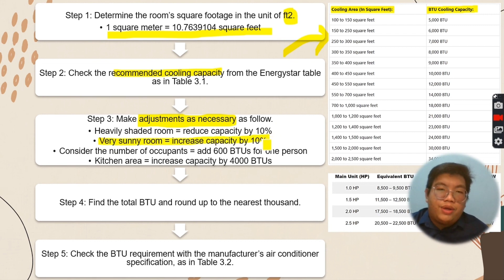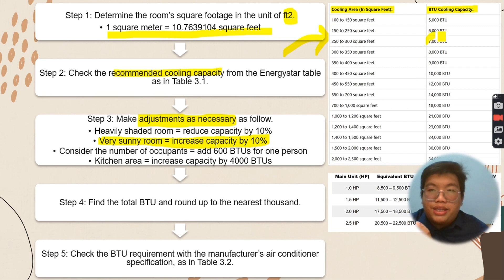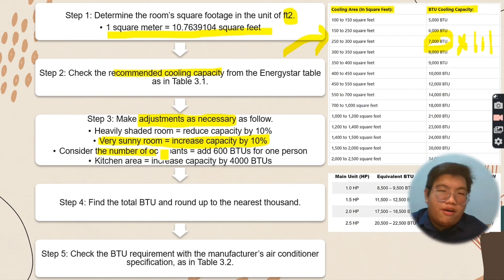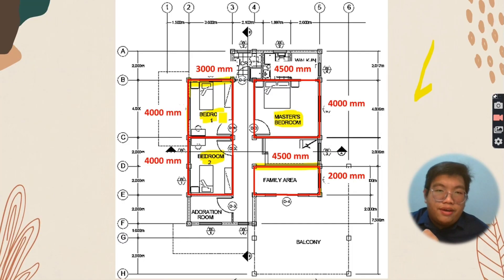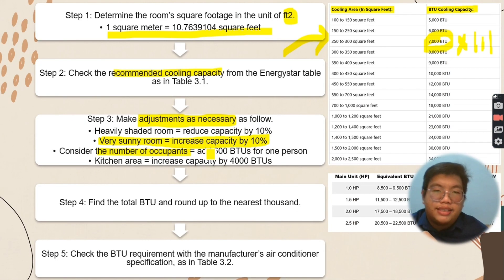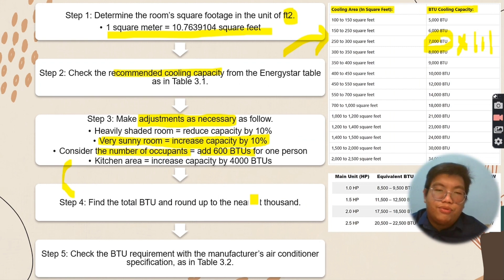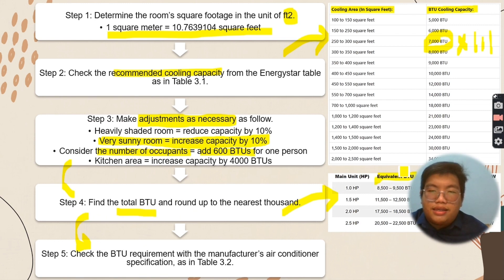In our case, I assume it is a very sunny room, so we need to increase the capacity by 10%, meaning we multiply the BTU cooling capacity — for example, 7,000 BTU — by 1.1. I also consider the number of occupants: for bedrooms and master bedroom it is 2, and for the family area it is 5, so we adjust by adding 600 BTU per person. After that, we apply the total BTU and round up to the nearest 1,000, then check the BTU requirement from the table.